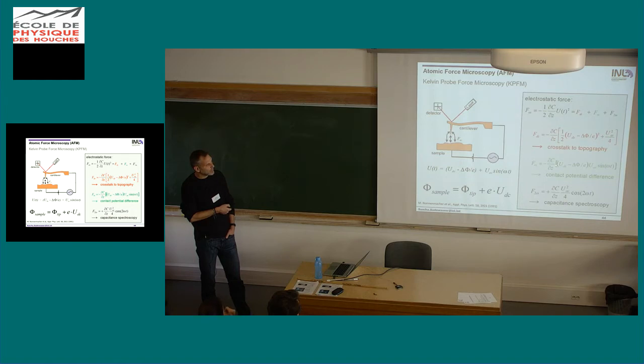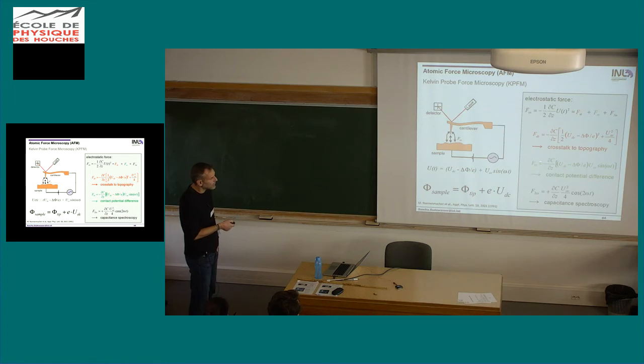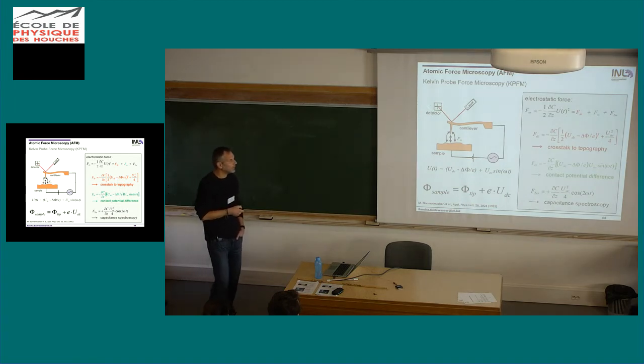And this disappears exactly when the DC bias that we apply, this part here, corresponds to the contact potential difference, to the difference in work function between the tip and the sample. So this term becomes zero, the force gets zero, there's no more oscillation at this frequency, and we detect this by using the lock-in on the photodetector here. So the controller adjusts the DC bias to the contact potential difference. Contact potential difference was the difference between sample and tip work function. So if we write this as the work function of the sample, then that equals the work function of the tip plus the DC bias that we apply.